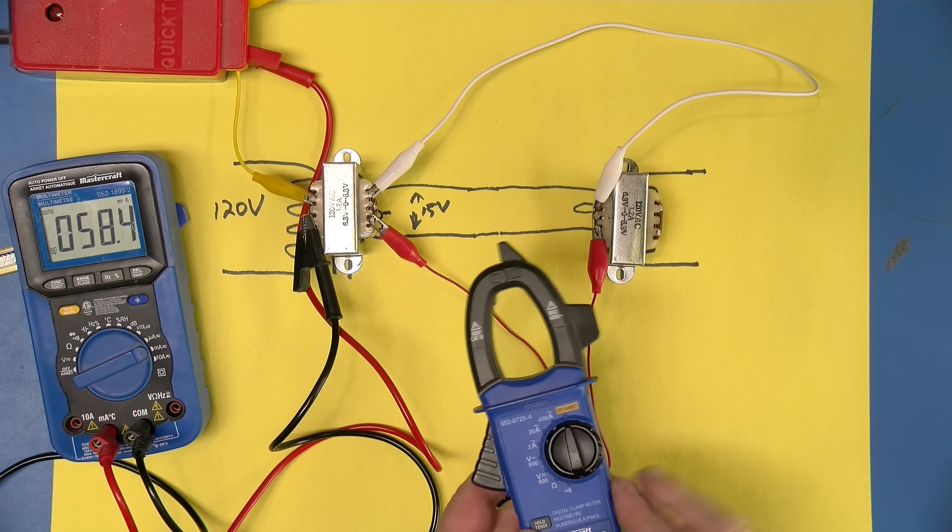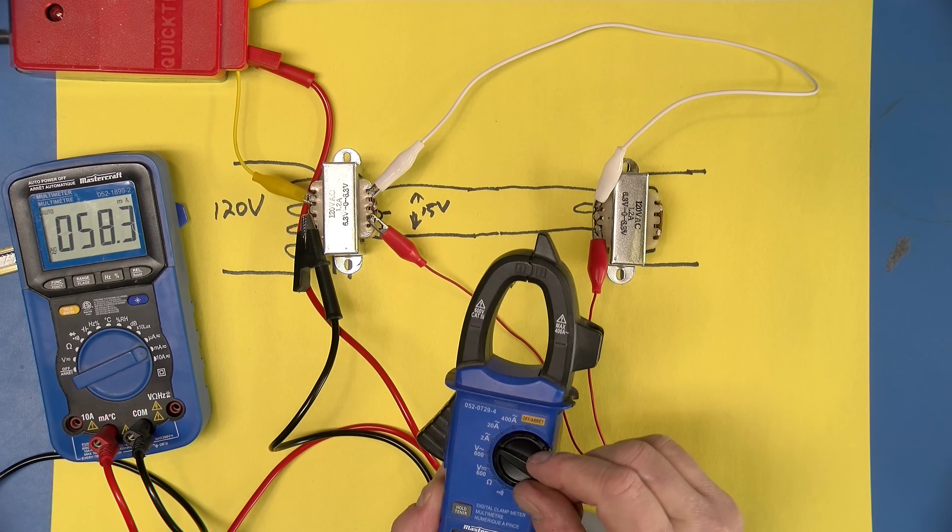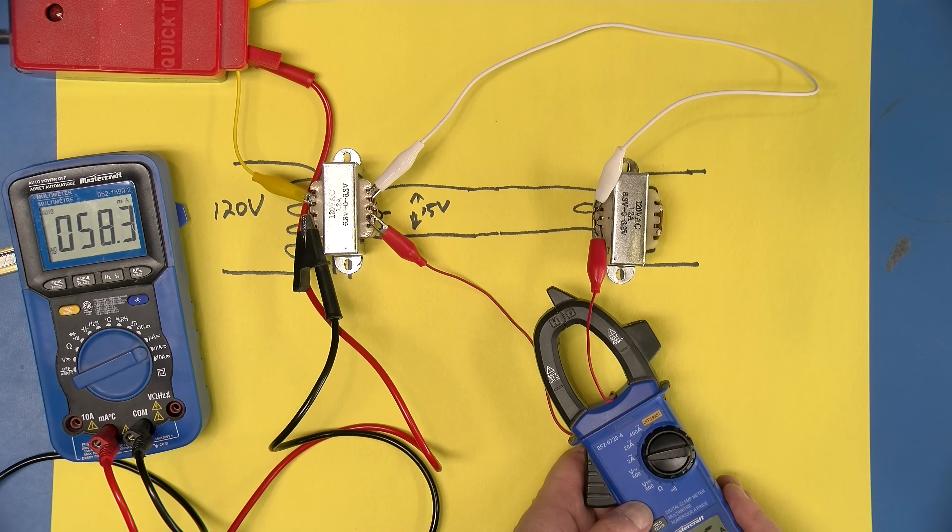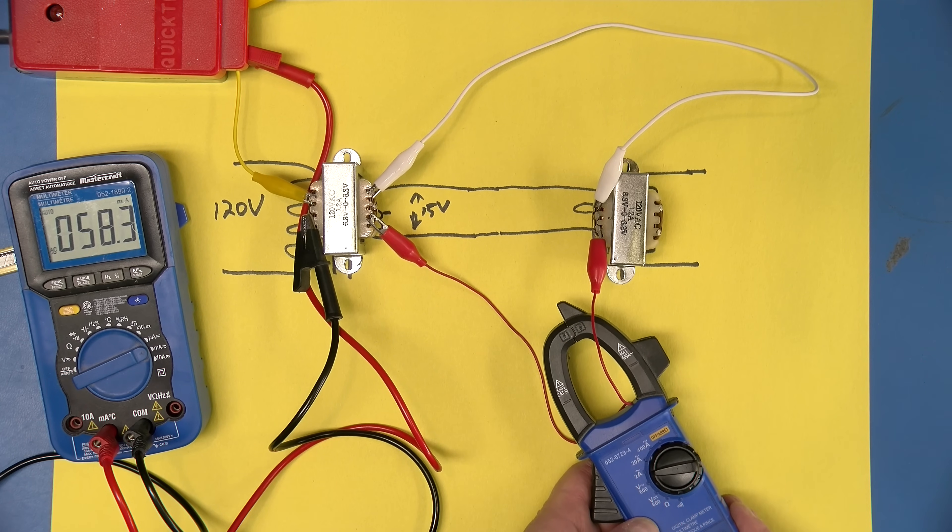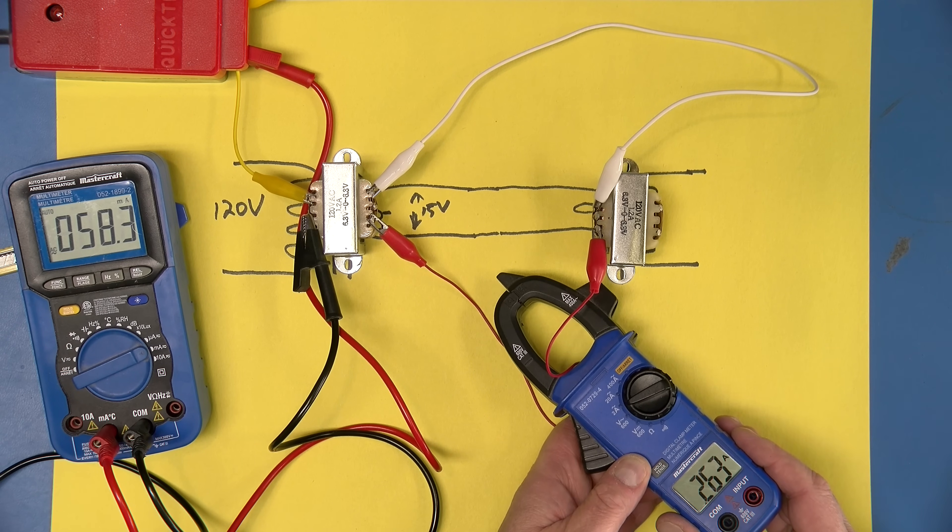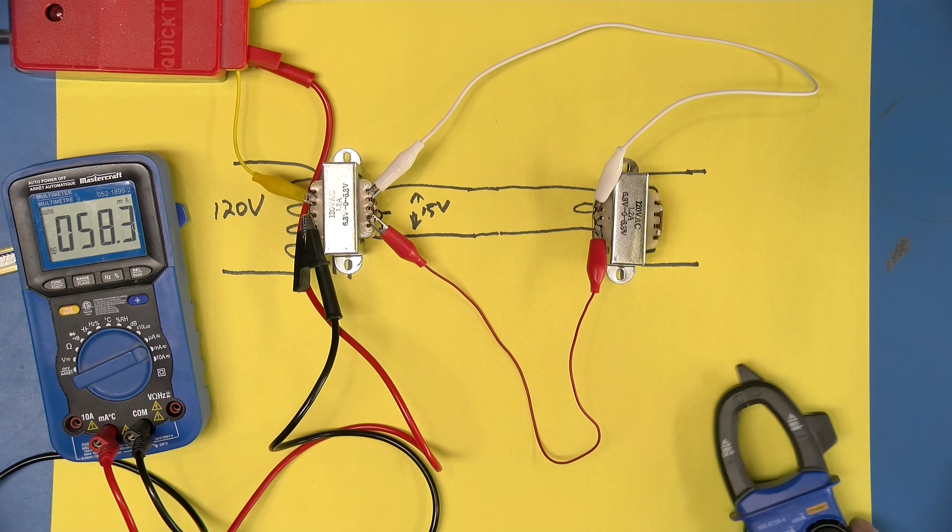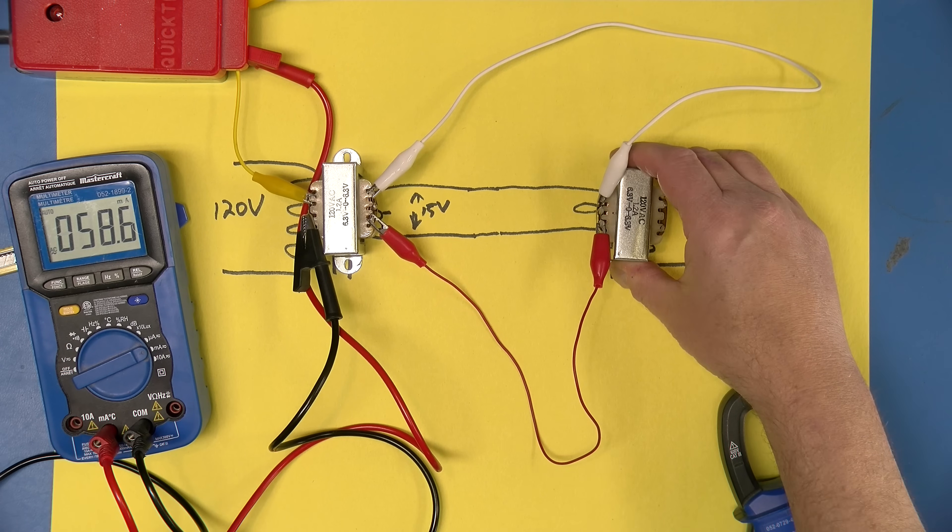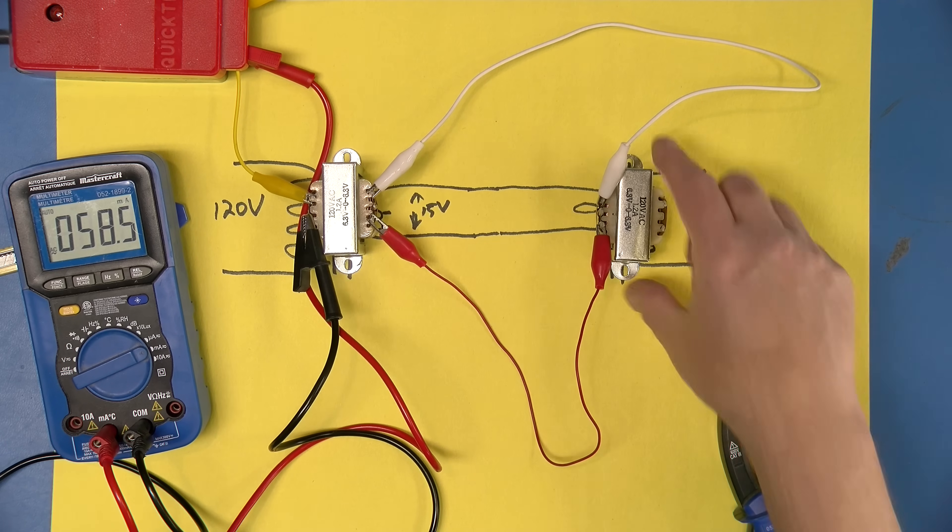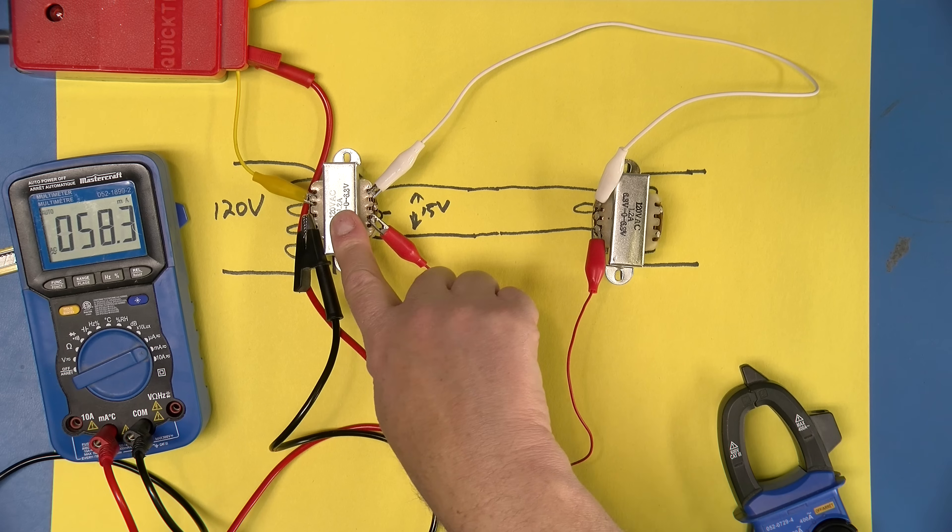And so what we'll do is use this nice little ammeter, clip-on ammeter, and see if we can measure what the current going into the second transformer is. And there we go, about 0.265 amps. That's almost exactly what we predicted. And all that really means is we are now energizing this transformer or magnetizing it in the same way we're magnetizing that one. But all of that magnetizing current has to come from the first transformer.